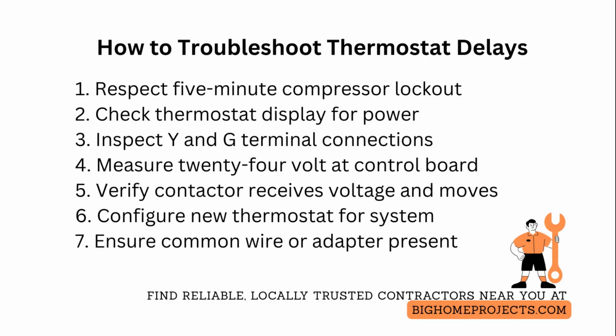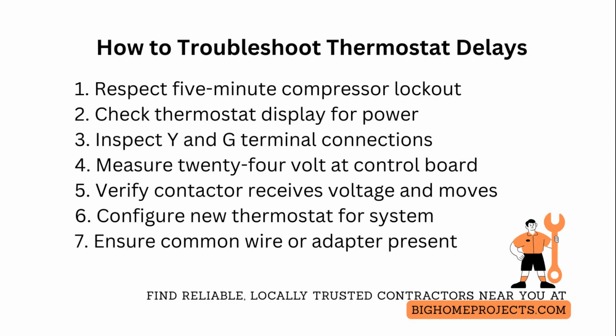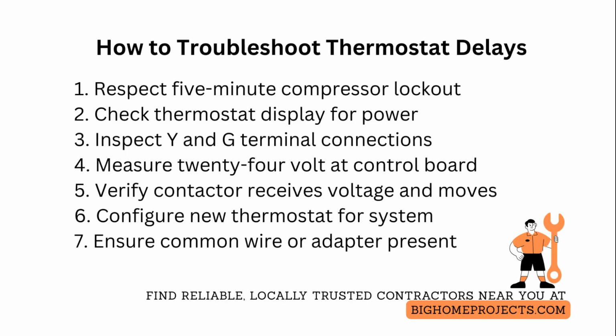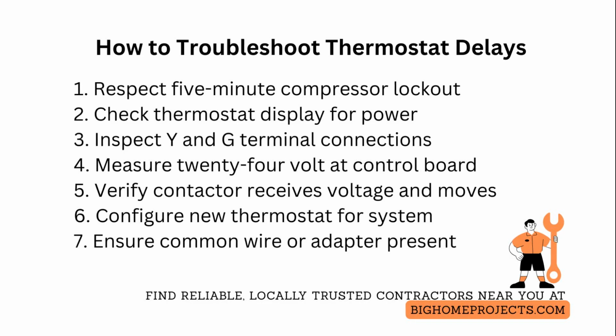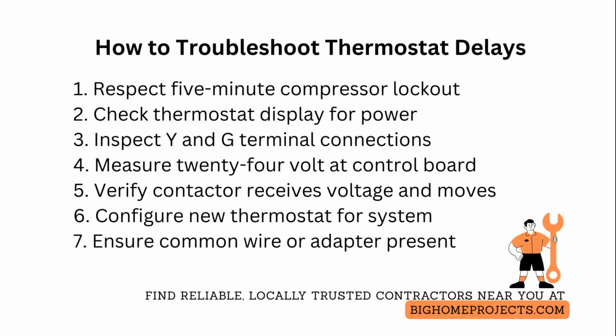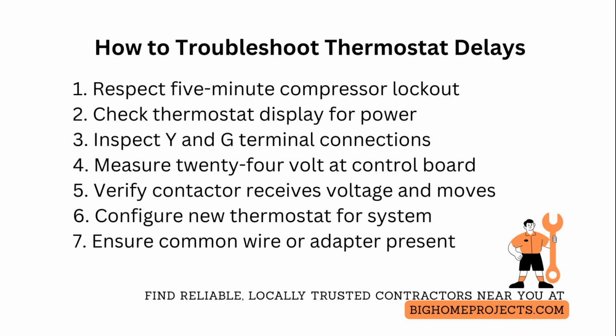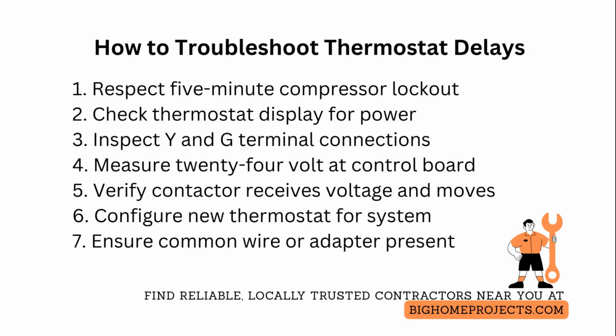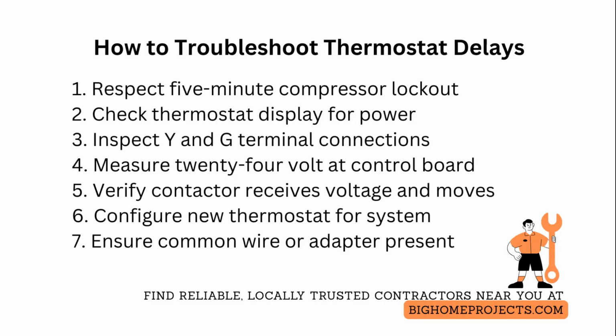Next, confirm the thermostat itself is behaving. A steady display, proper backlight, or normal icons indicate it is powered. A blinking display often means low battery or loss of power from the 24-volt transformer. Remove the thermostat from its base to inspect the terminal connections. Make sure the wires to the cooling call lead labeled Y and the fan call lead labeled G are snug, corrosion-free, and on the correct terminals. A loose Y wire can energize the relay intermittently.